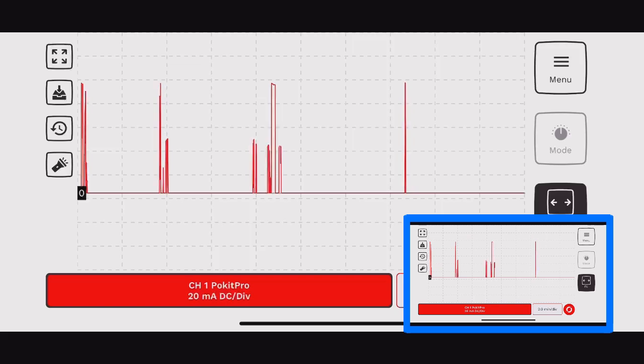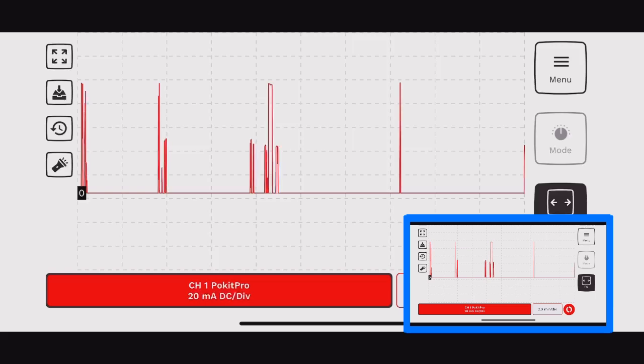You have to depend on a live circuit and use logging meters, as I'm showing you on the screen now. And let me go ahead and hit this again to show you what happens when it sees a short in there. You'll notice, there it goes.